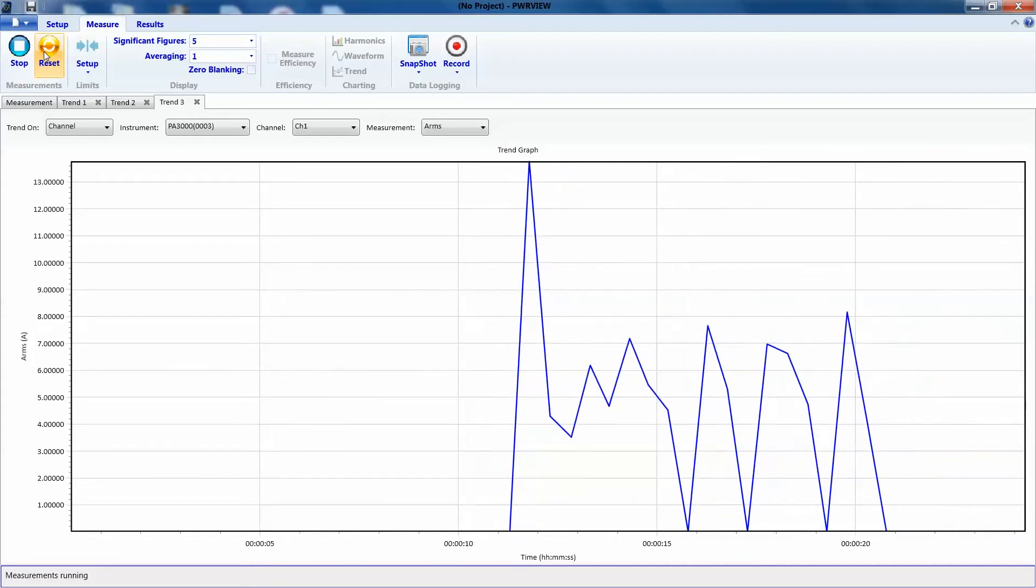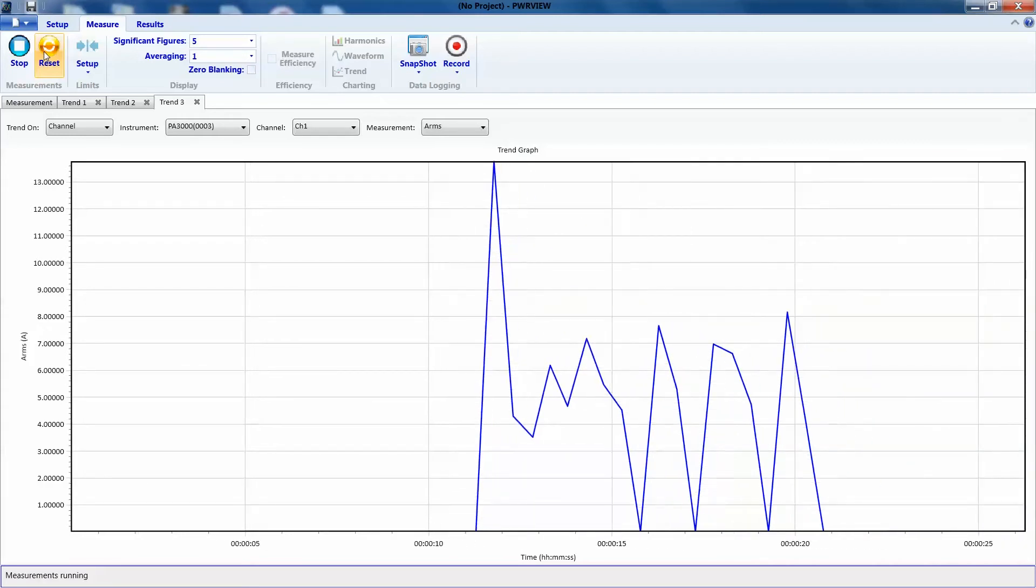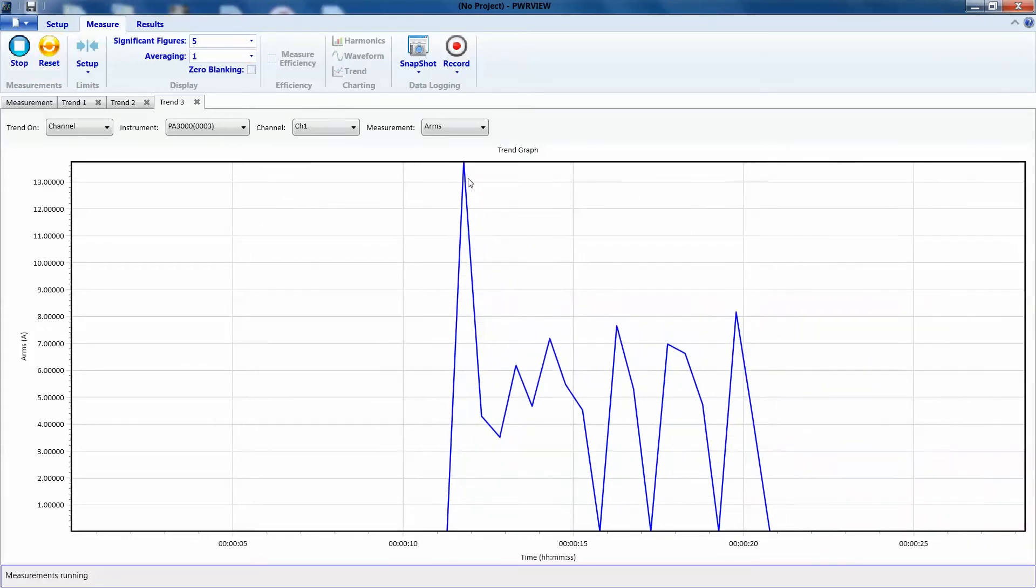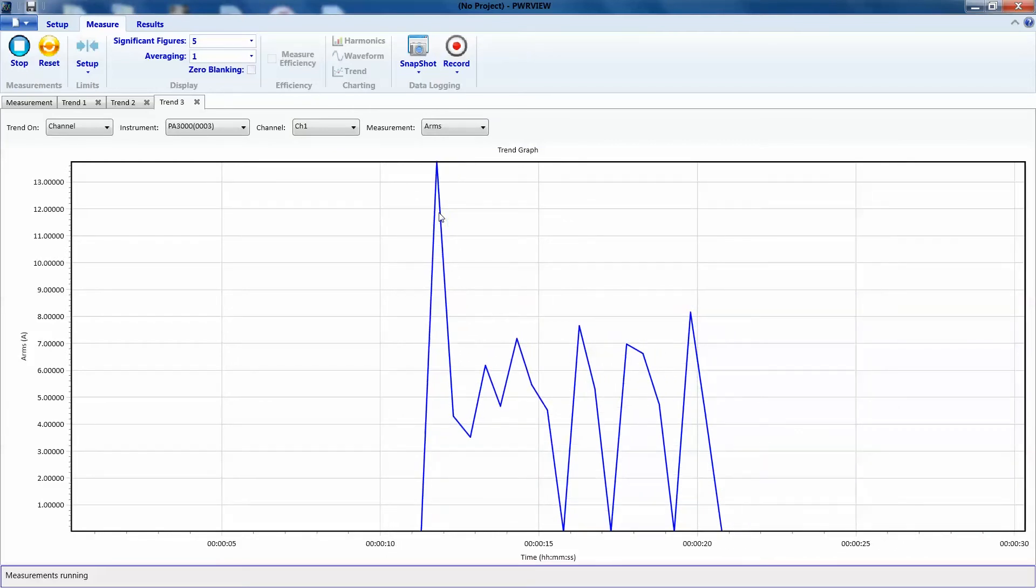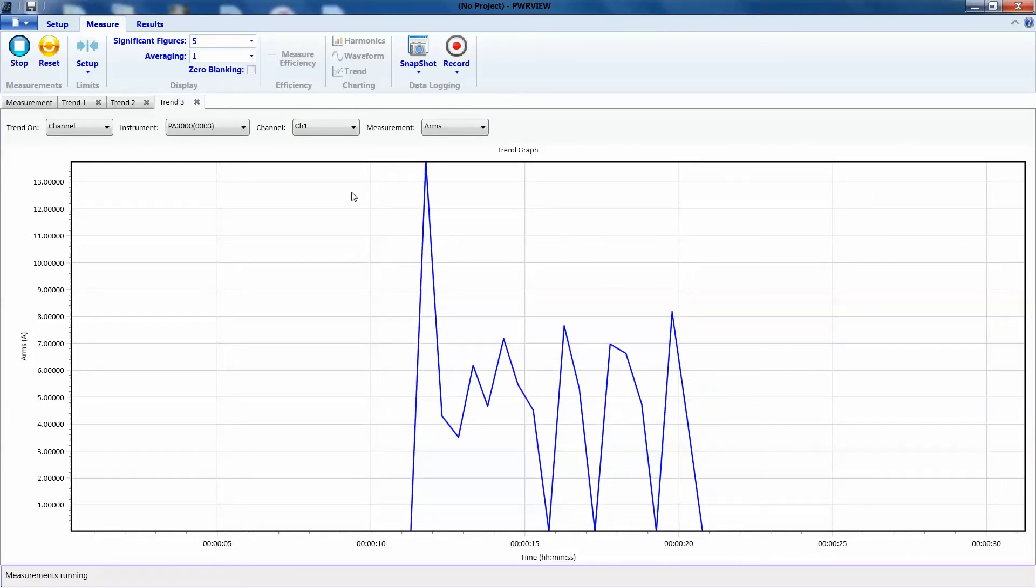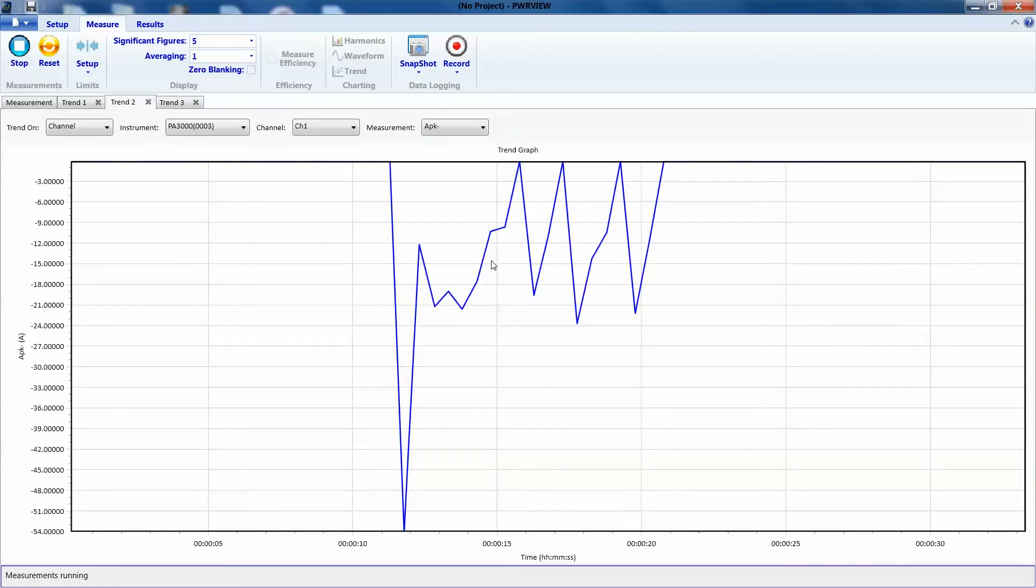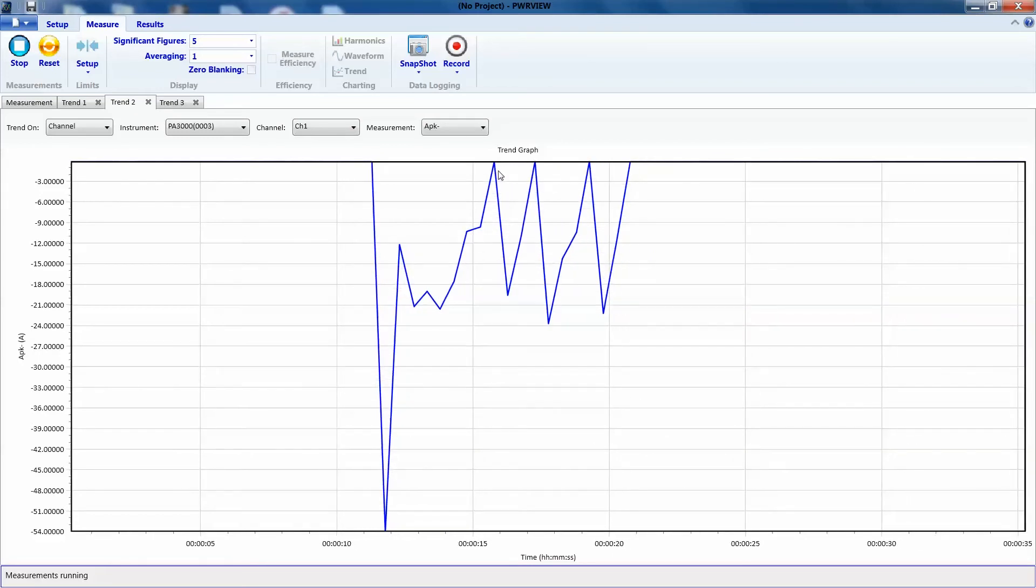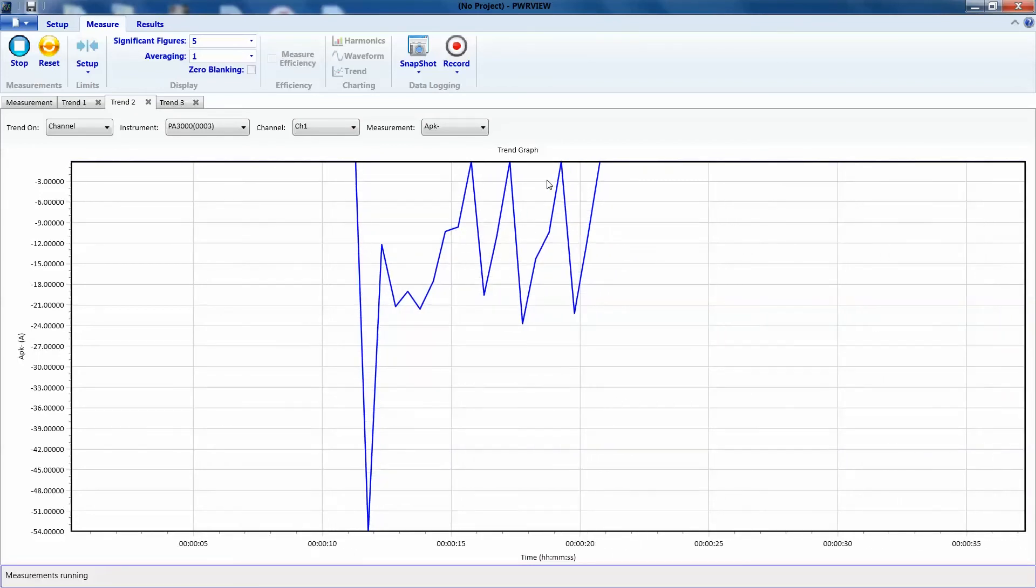There you go. So, let's check how much inrush current we got. As you can see on the screen now, the maximum ARMS value was about 13 amps. Let's go to the peak values. There you have it. You can see all those inrush currents coming in.